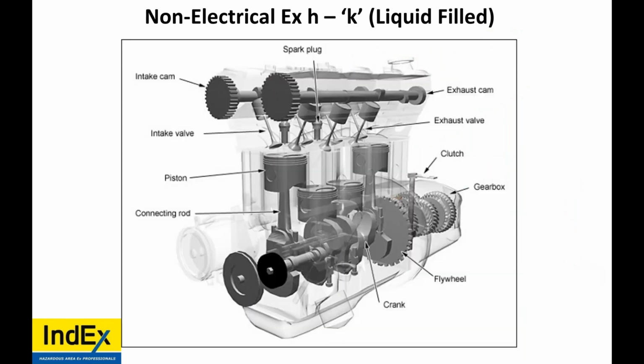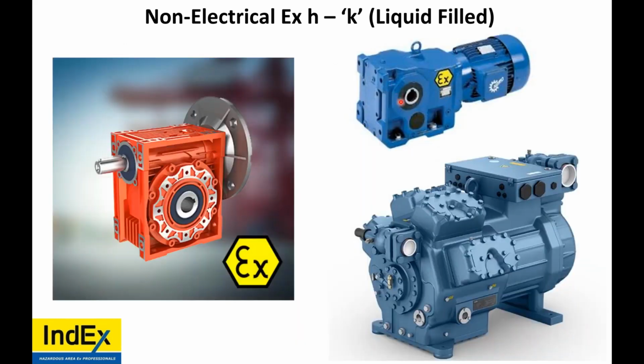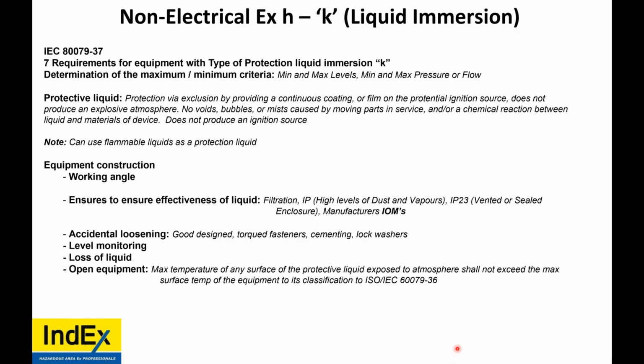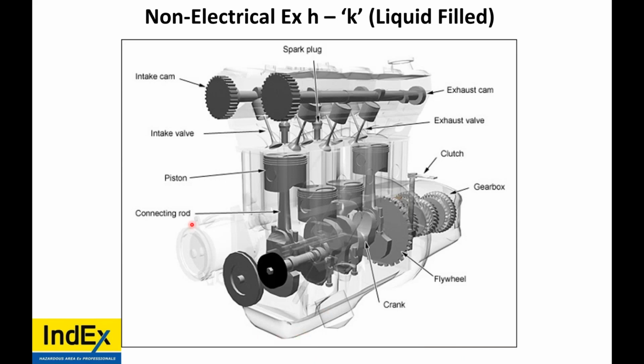So how does it work? Well, think of just like a motor. You have camshafts or gears. Well, in a motor, all these are coated in oil. So the same thing for these gearboxes. They can be EXK, liquid immersion type, okay? So what are important considerations? Well, to IEC ISO 80079-37, you need to consider minimum and maximum criteria of the liquid, the minimum and maximum levels, the minimum and maximum pressure or flow as well, because it will be moving around like the engine of a motor. The oil will move around.